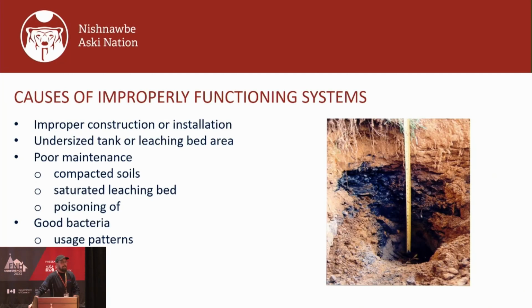The thing with septic systems is they are not built with an infinite lifespan. They are built with a lifespan of 25 to 30 years typically. It's like any other system in a lot of the communities that we work with. If you are overcrowding and overloading a system, you are going to be overworking the bacteria in that system. So if you have a system that's only designed to service 6 people and it's servicing 12 people, that's twice as much food for the bacteria. The bacteria will probably grow twice as fast and you'll have twice as many bacteria plugging up the holes in the soil. So you're going to get this failure hydraulically because the bacteria clog up the holes in the soil pores.